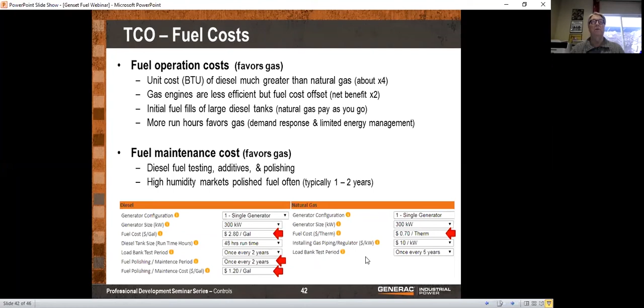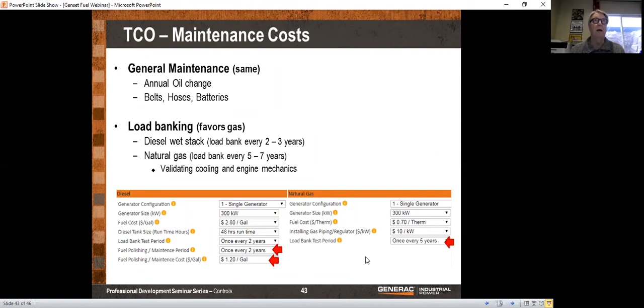Load banking, you have to load bank a diesel every 2 to 3 years because they wet stack. They get carbon deposits in there. Natural gas doesn't wet stack. So we recommend you probably load bank 5 to 7 years just to make sure everything's in good shape. But that's another cost savings. Somebody bringing out a load bank and testing your generator, that's kind of an expensive item.